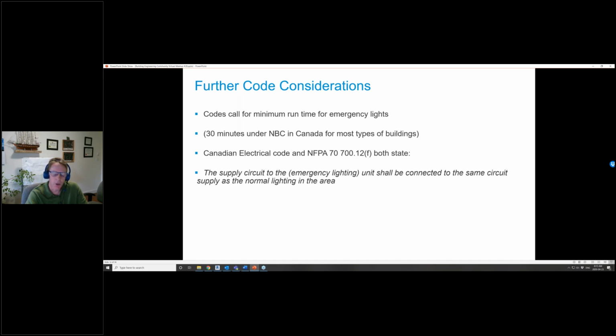And here in British Columbia, we're seeing the inspectors actually pay attention to this. The way they test the systems, and the way we also test, is we switch off the breakers serving the lighting to the area, and we expect to see the emergency lighting come on. So as you design, this particular clause will be important, and I'll talk about this a little more as we get into some of the systems.